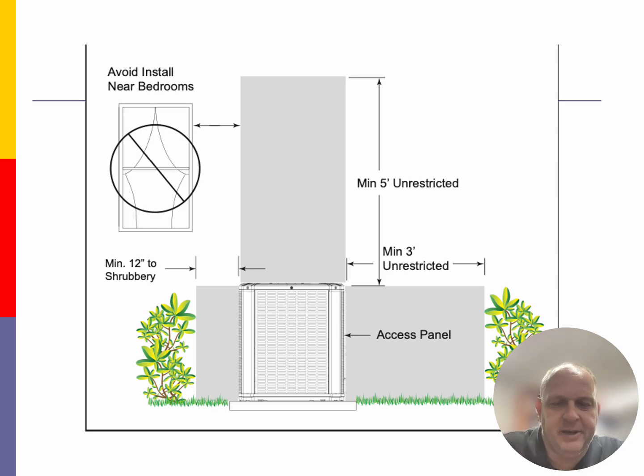In today's world, our air conditioners are a lot quieter than they used to be, so this doesn't tend to be a problem, but we want to try to avoid being near a bedroom just in case that unit would bug those individuals while they're sleeping. Keep all vegetation away from the unit, at least a foot. I've seen people plant things right up against it because they don't want the ugliness of the units, especially today. These things are 5 feet tall, horrible looking on the sides of the buildings. But keep the shrubbery away. We need that airflow to come in.